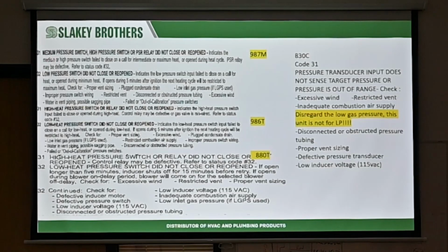Medium 31. This is on the 987M. Medium pressure switch, high pressure switch, or a PSR relay did not close or reopen. So pressure switches, like this one right here, there's 2 of them right side by side. If they stick, that's simple. You're just going to check continuity. So if the inducer motor is off and we think you're getting a fault because a switch is closed, you're checking for 24 volts.